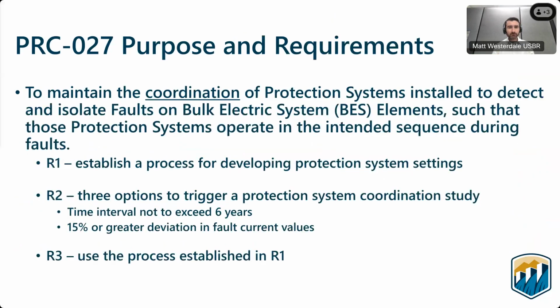Here's a quick overview of NERC standard PRC 27. Its primary purpose is to maintain coordination of protection systems installed to detect and isolate faults on the BES. The term coordination can mean different things to different people. For protective relay engineers, it often means things are operating in the right sequence. So if we have a fault out on a transmission line, the relays providing protection for that line operate first and only trip that line, and not relays or equipment behind it or on other systems that would take equipment offline that wasn't necessarily needed to isolate that fault.